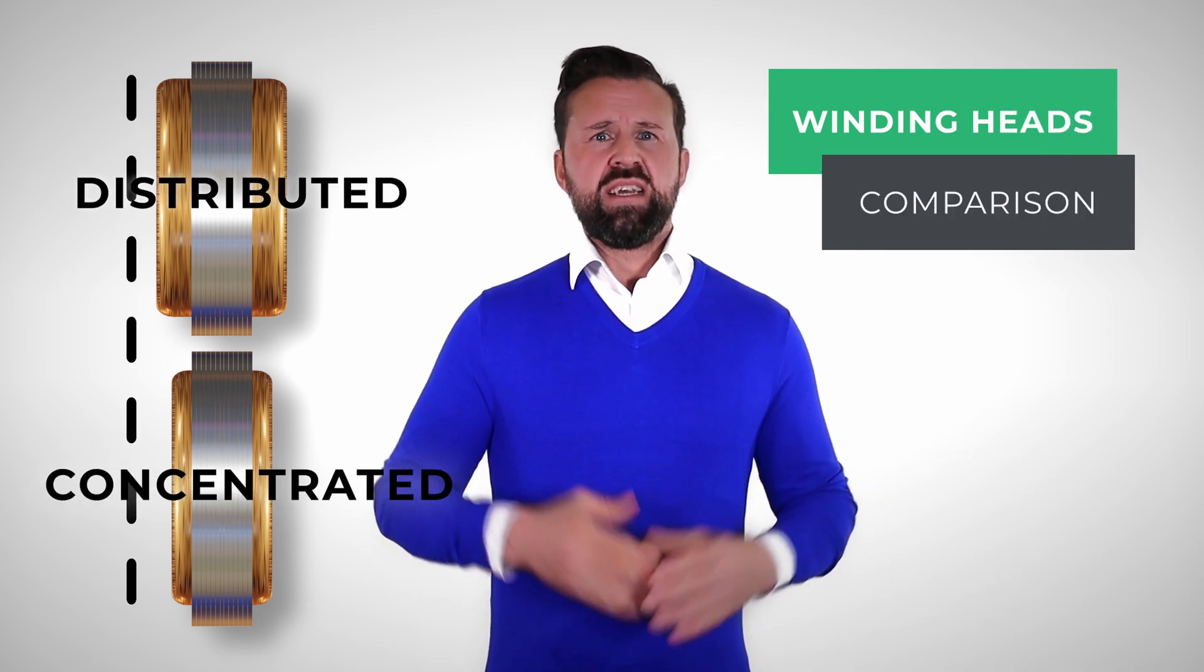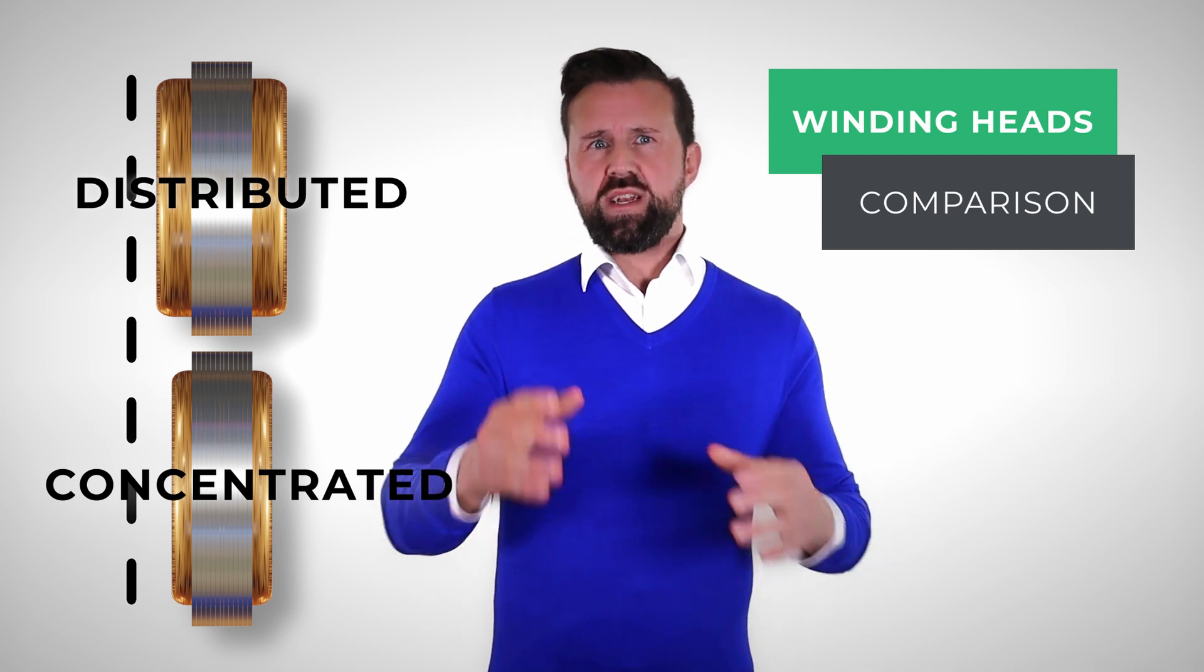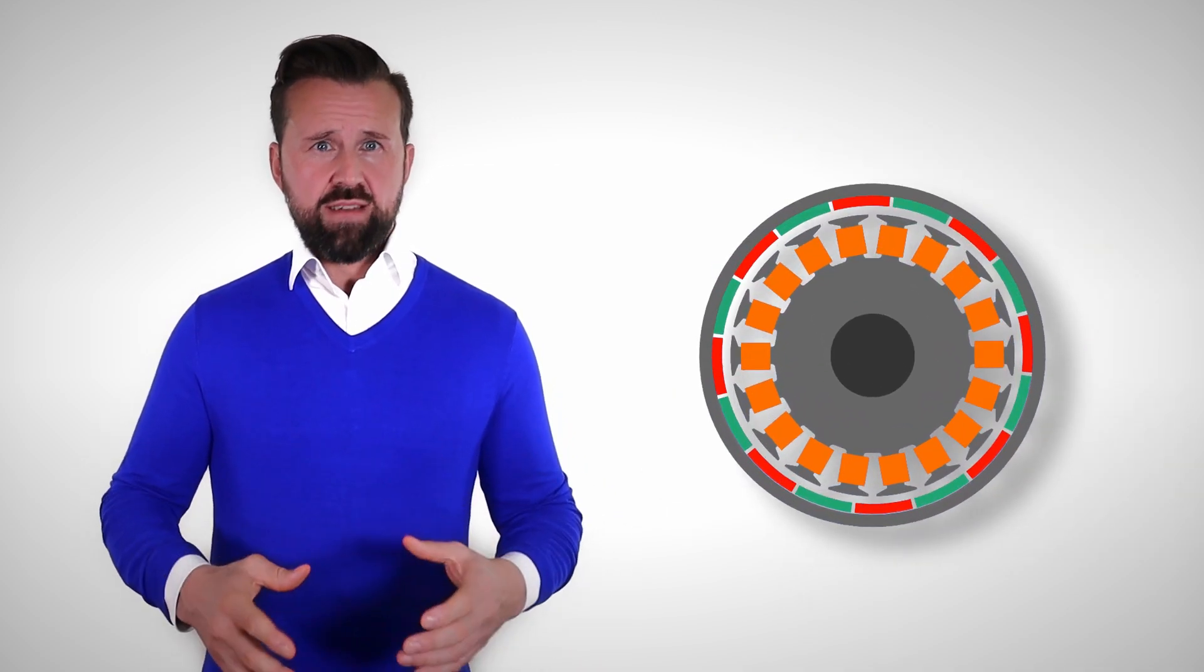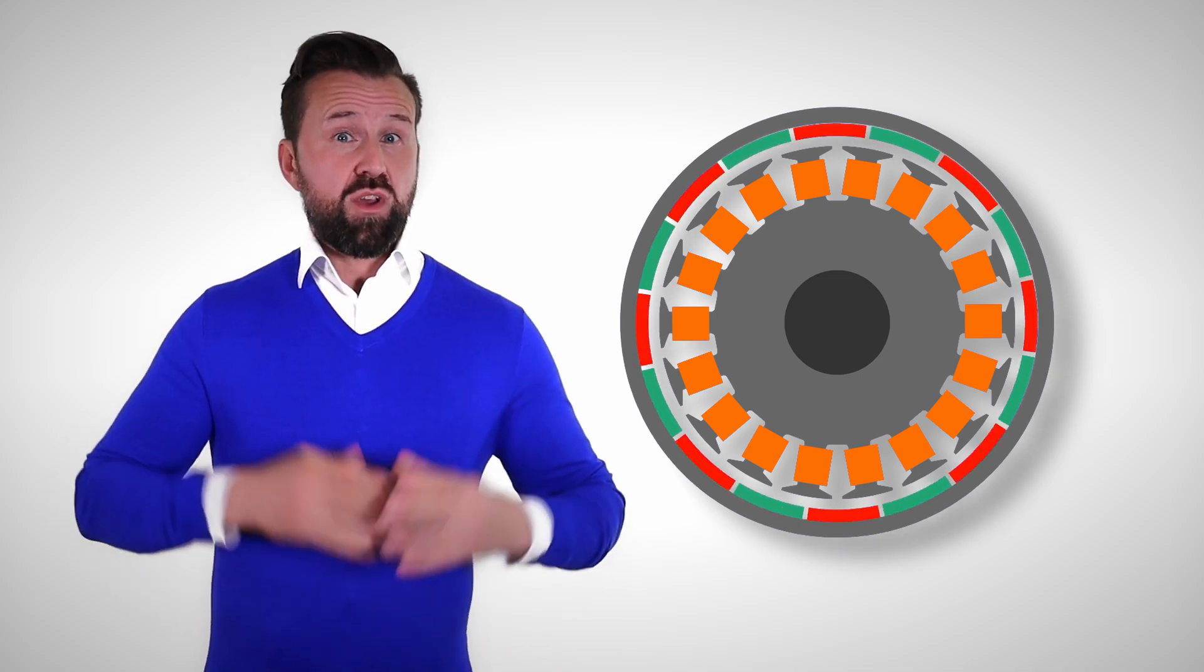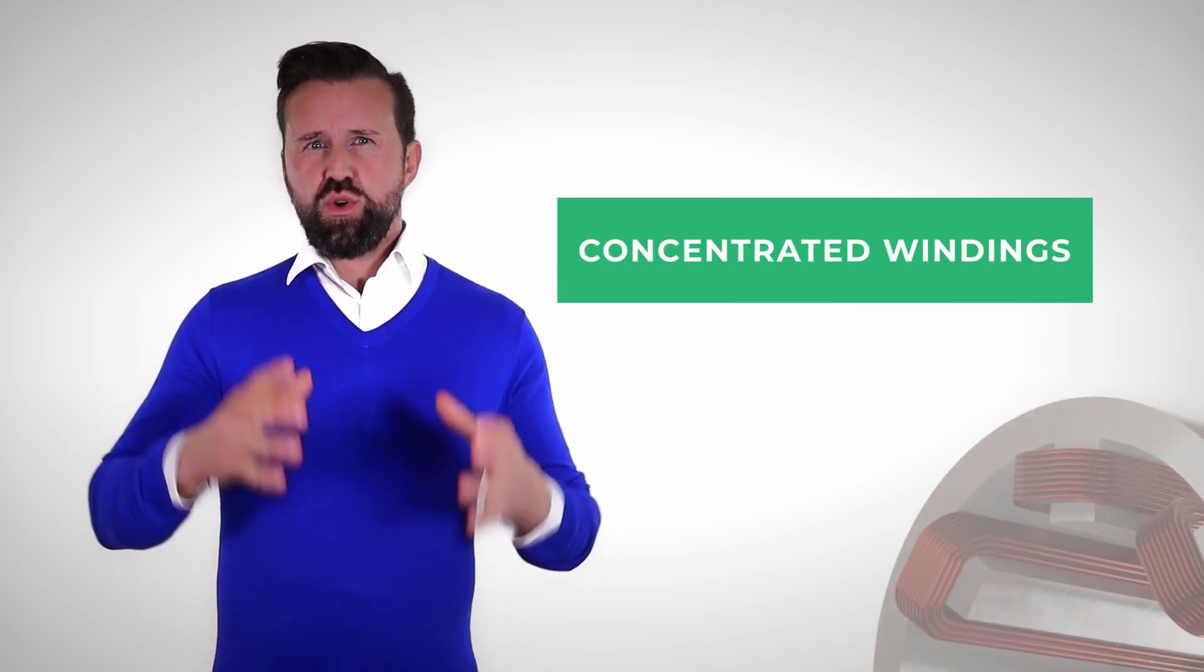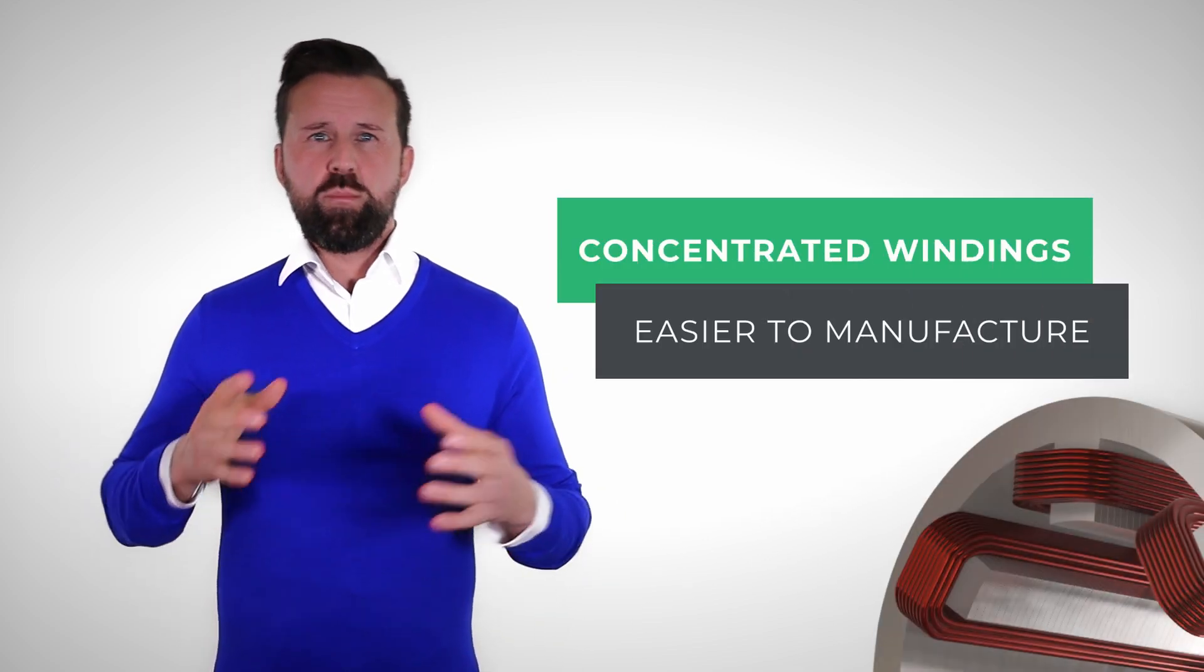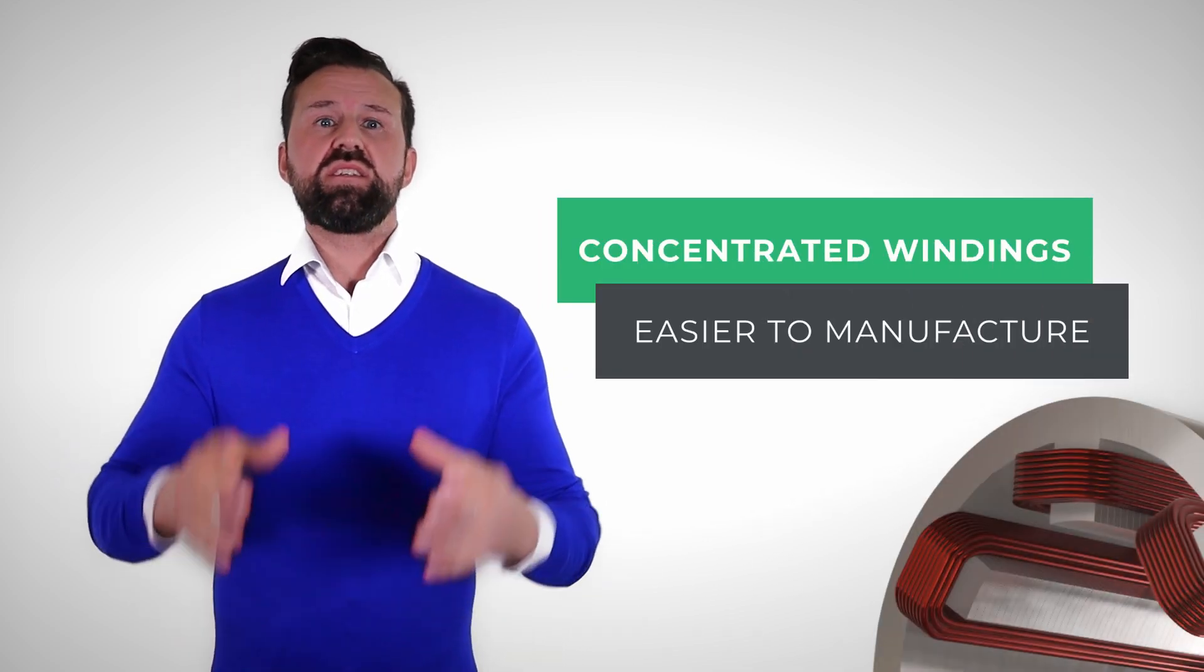Therefore, a concentrated winding is usually used for very short electrical motors. In this way, the ohmic losses from the winding head can be reduced. Wheel hub drives for bicycles are therefore almost always manufactured with concentrated windings, because they are short and have a large diameter. It is also easier and less expensive to manufacture a stator with a concentrated winding.